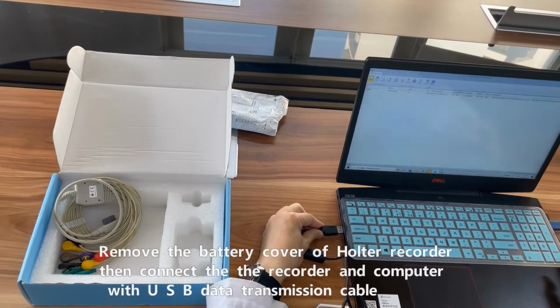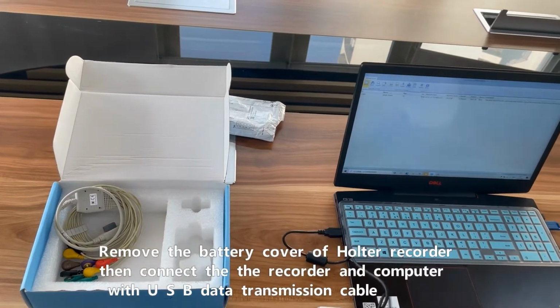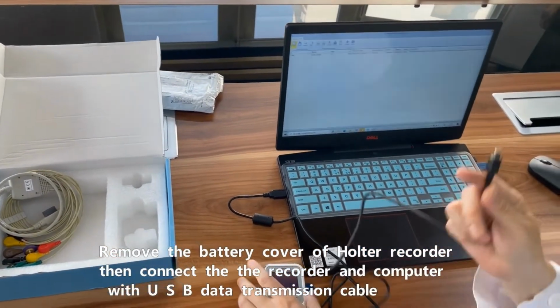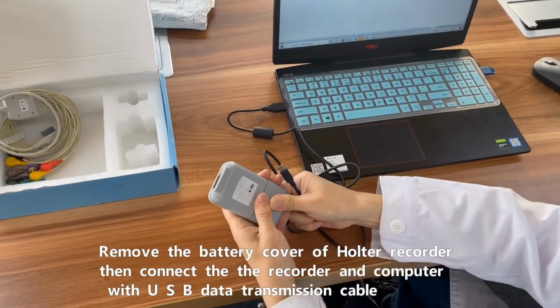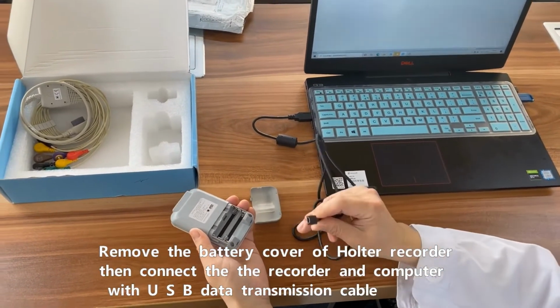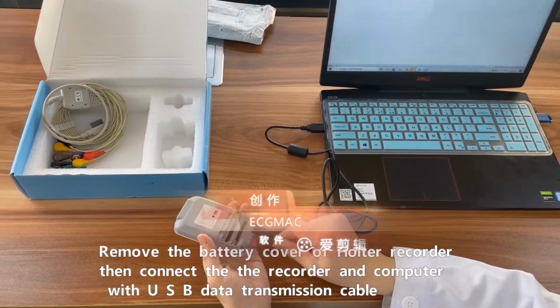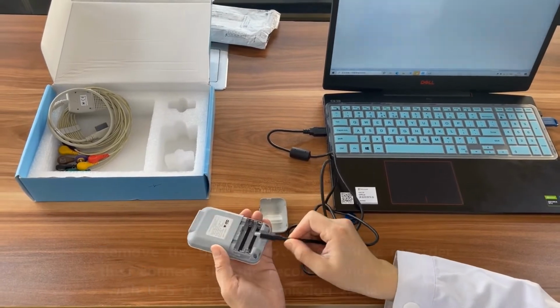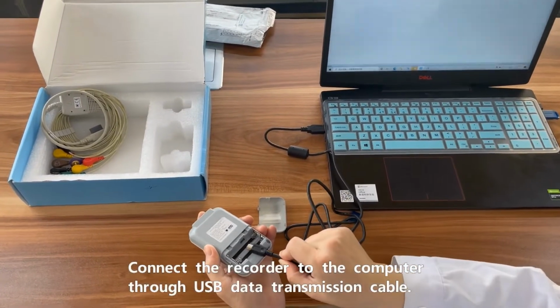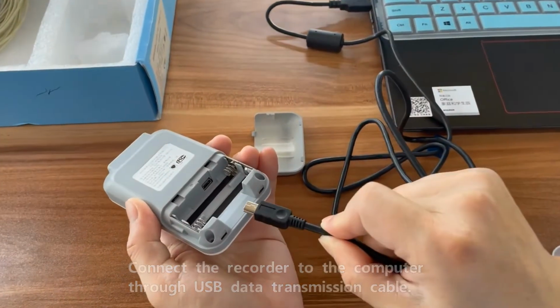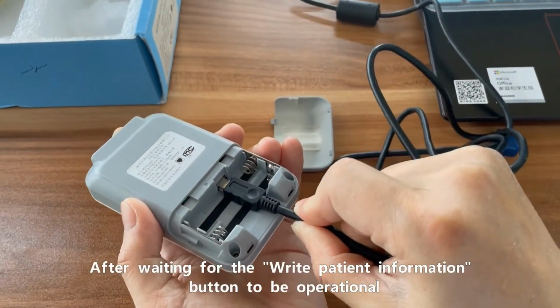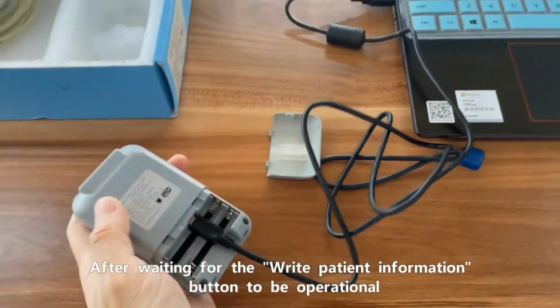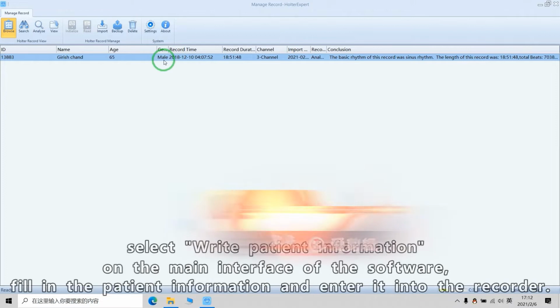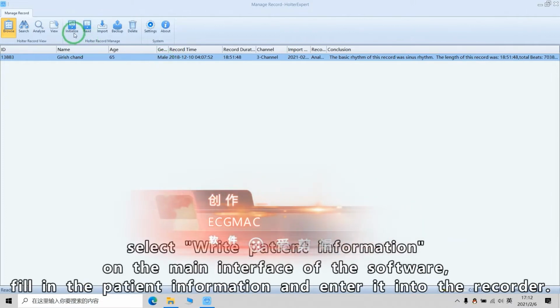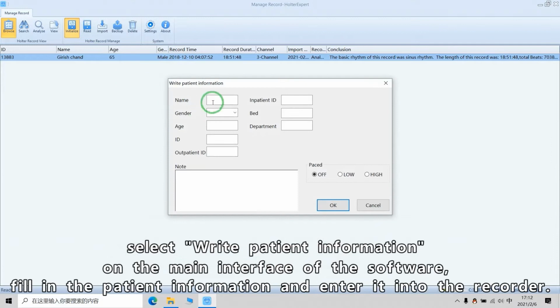Remove the battery cover of the Holter recorder, then connect the recorder and computer with the USB data transmission cable. After waiting for the Write Patient Information button to be operational, select Write Patient Information on the main interface of the software. Fill in the patient information and enter it into the recorder.